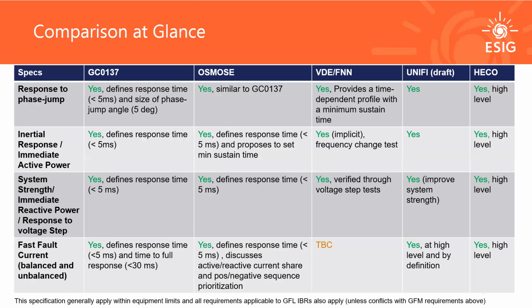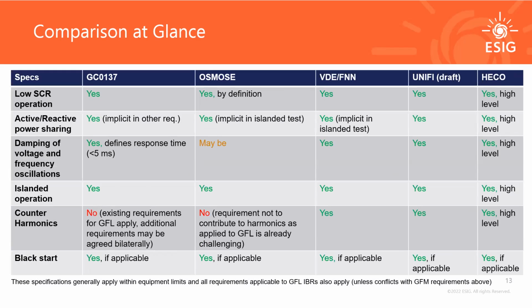So you look across the requirements that I just mentioned, and in green, it's all yes. And so this high level is required there. It may have more details or fewer details in it. And so they all require some kind of response to phase jump, inertial or immediate active power injection. System strength is called that in some requirements, and in others it is immediate reactive power injection. Fast fault current: I couldn't find in the VDE requirement how the fast fault current injection is tested, but I might have missed it. So I just said to be confirmed there.